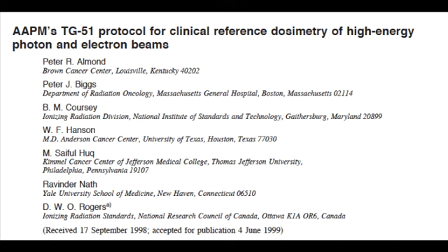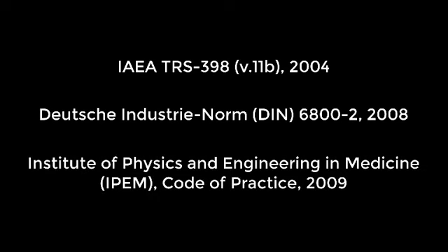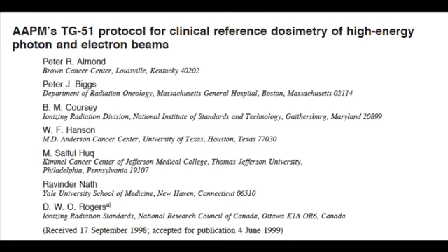I'd like to mention a couple things about TG51. Number one, it's not the only dose calibration protocol out there. There are others. There's TRS 398 from the International Atomic Energy Agency. There's something from the Deutsche Industrie Norm, a German group. And then there's something from the Institute of Physics and Engineering in Medicine, IPEM, which is a UK group, and they have a protocol as well. So what I'm going to show here is TG51, but they're very similar. All these protocols have slightly different nomenclature, but the concepts are similar.